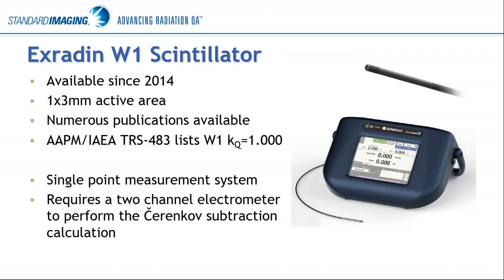One of the key publications recently is the IAEA and AAPM joint publication on small field dosimetry — Technical Report Series 483 — which shows the W1 in a number of their tables. In every single one, it is the only detector that across the board for every field size, every energy, and every machine shows a KQ value of one. This was designed to be just a single point measurement system.